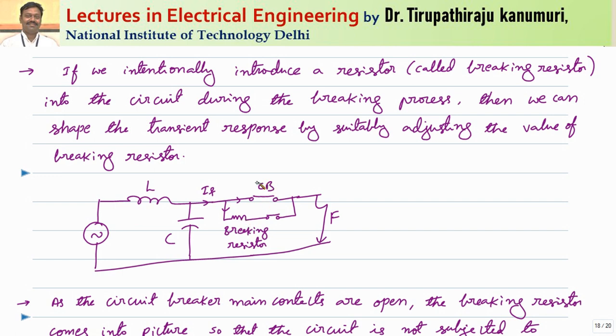As some current is bypassed, the current passing through the circuit breaker decreases, which automatically speeds up the deionization process. Because the deionization process speeds up, the resistance between the circuit breaker contacts increases. Consequently, more current bypasses through the breaker resistance. This is a cumulative process: after some time, no current passes through the circuit breaker because the dielectric strength of the material has cumulatively increased, and the entire current is bypassed through the breaking resistor.